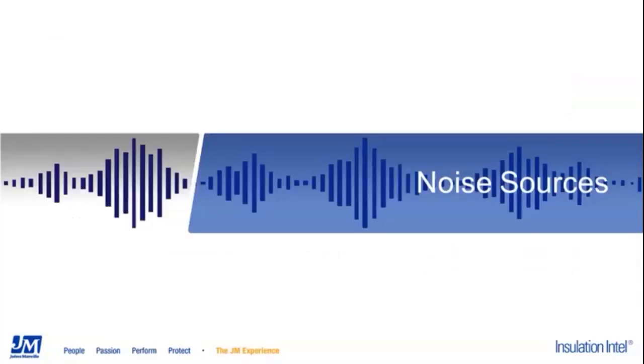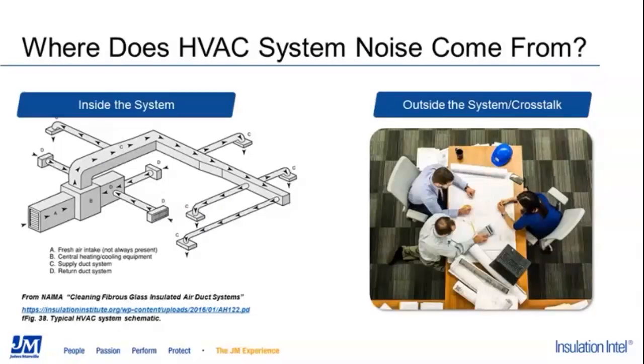So let's spend a little time trying to understand where noise comes from and how it can enter noise-sensitive spaces. We're mostly looking at air handler systems, rooftop units, makeup air units, exhaust fans, etc. in this presentation. But noise can also come from other mechanical equipment, including chillers, pumps, condensing units, swamp coolers, etc. And some of these can be full of tones and very difficult acoustically to deal with, especially at property lines regarding city, county, or state noise ordinances. But we're going to focus on air handlers.